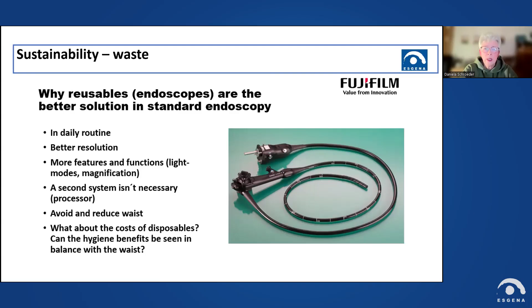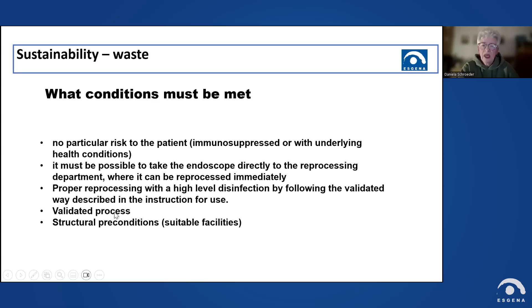But the following conditions must be met. There is no particular risk for the patient in case of an immune suppressed situation. We need to reprocess the endoscope directly after the use, so that needs to be sure. And we need to follow high-level disinfection by following the validated process described in our instructions for use, or your validated process. And you need the best structural preconditions, so suitable facilities.